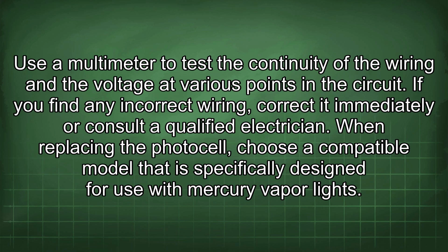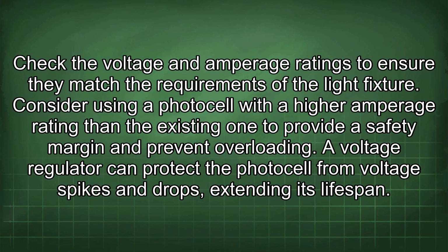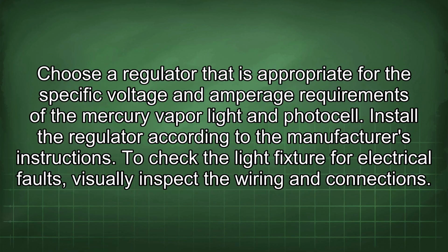When replacing the photocell, choose a compatible model that is specifically designed for use with mercury vapor lights. Check the voltage and amperage ratings to ensure they match the requirements of the light fixture. Consider using a photocell with a higher amperage rating than the existing one to provide a safety margin and prevent overloading. A voltage regulator can protect the photocell from voltage spikes and drops, extending its lifespan. Choose a regulator that is appropriate for the specific voltage and amperage requirements of the mercury vapor light and photocell. Install the regulator according to the manufacturer's instructions.